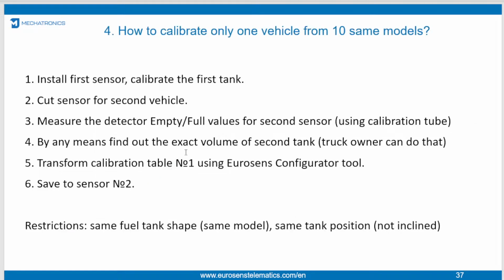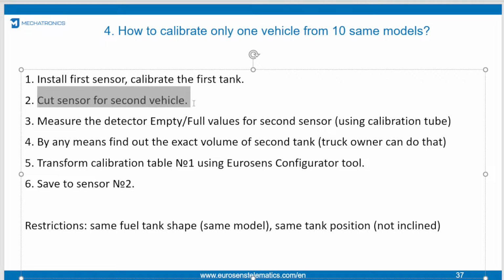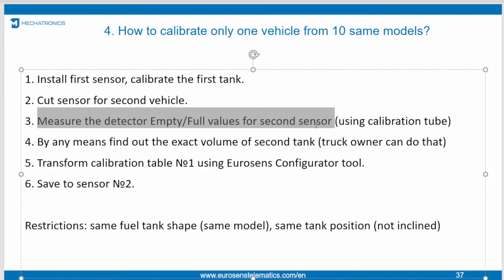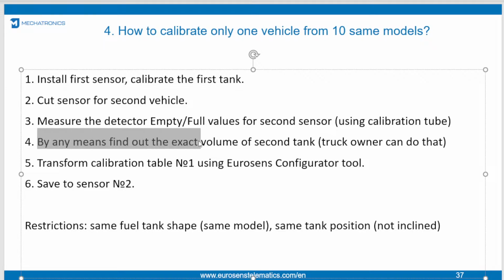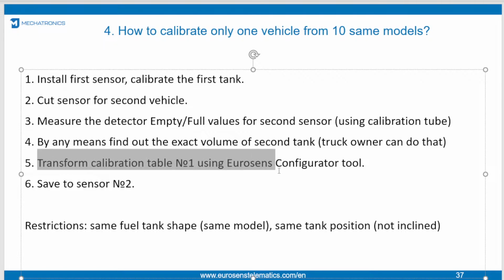So, to resume how to do that: you install the first sensor and calibrate the first tank by portions. Then you cut the sensor for the second vehicle. Then you measure detector empty and full values for the second sensor in the tube, same as for sensor calibration, empty and full. And it's very, very good if you can know the exact volume of the second tank, because it can be different from the first one. Then you transform the table using our configurator and save it into the sensor.